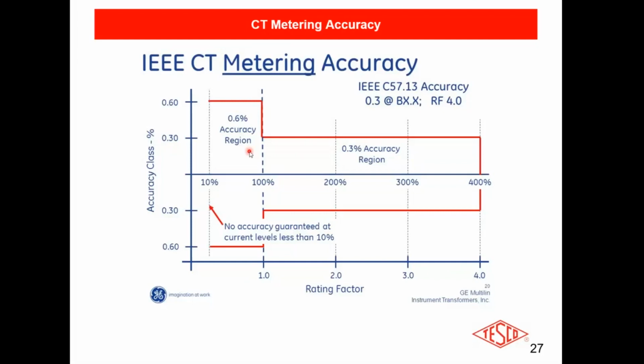number of windings. So if you exceed the thermal rating factor, you heat that wire up and you can start to break down. Because it expands, it's going to put a lot of force on that insulation, and eventually it's going to crack and break it and can short out. All right, so hopefully if that answered the question, just type a yes in there. If it didn't, just keep asking, Matthew.